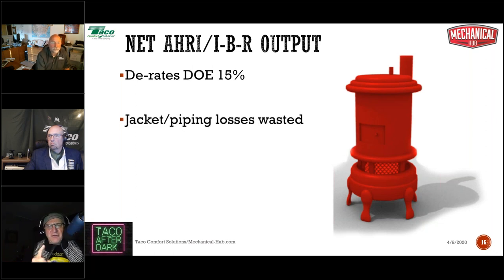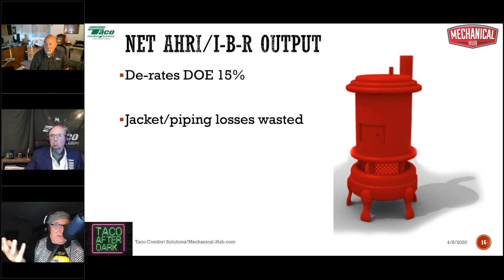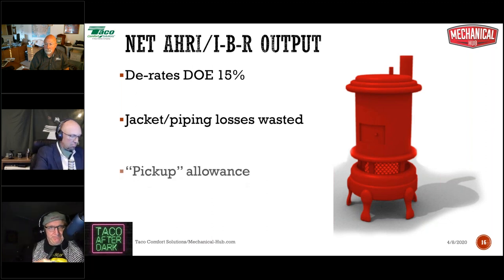Well, first off, there's two elements here. First off, IBR, old school, back in the old days, they would presume that the boiler was installed in an unheated, unconditioned basement. All right, unheated, unconditioned basement. So any jacket losses and piping losses, well, yes, they did temper the basement, were considered wasted, not usable heat. They didn't heat anything where you lived. So that was a portion of the 15%, jacket losses and piping losses considered wasted.